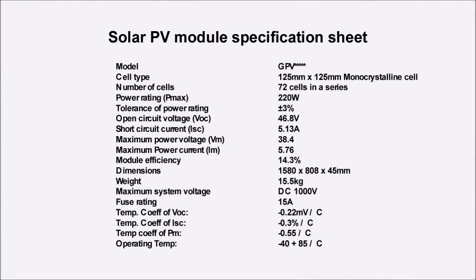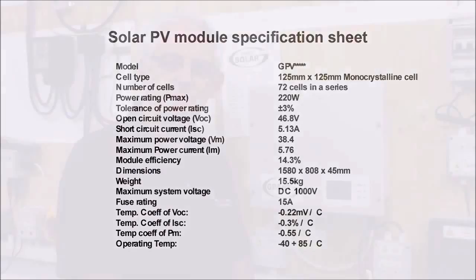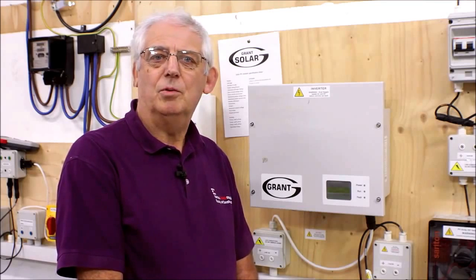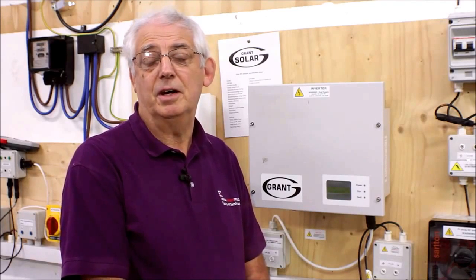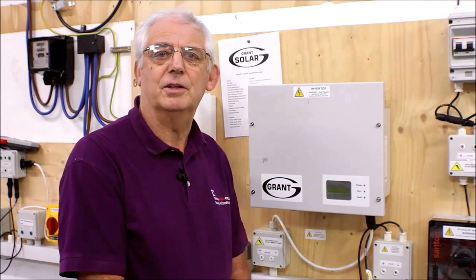calculation. To ensure our PV system is working correctly, we also need to check the short circuit current to make sure that it coincides with the amount of sunlight we get. Our panels are rated at a short circuit current of 5.76 amps. And what that means is that they'll generate 5.76 amps when the sunlight is producing an irradiance of 1,000 watts per square metre. Now, of course, our sunlight isn't always going to produce 1,000 watts per square metre. Sometimes it's going to be far less. So we need to carry out a calculation.